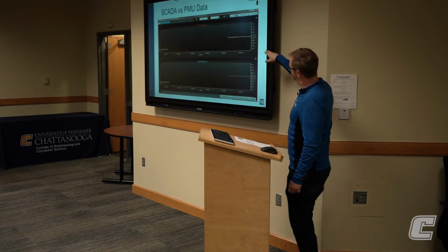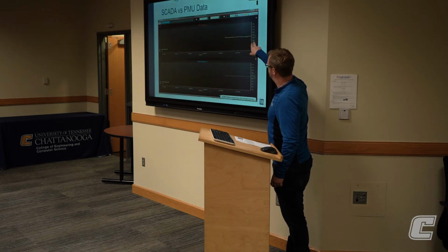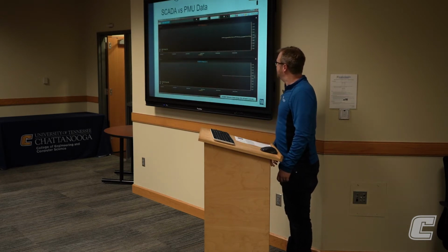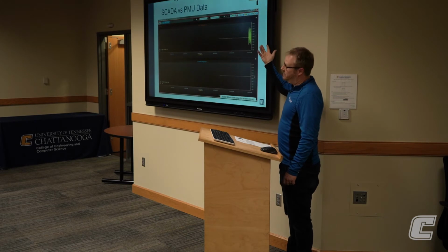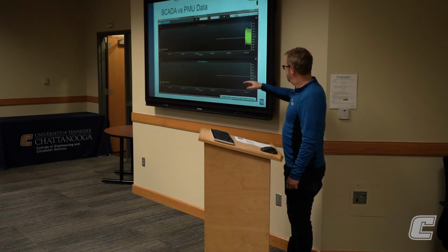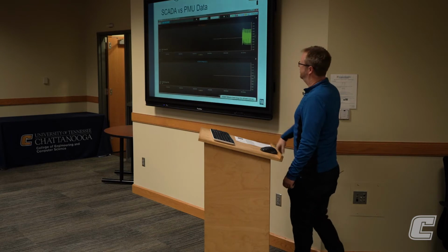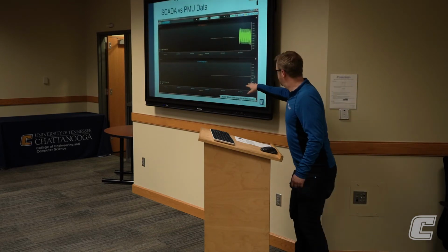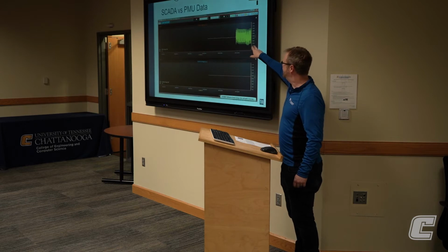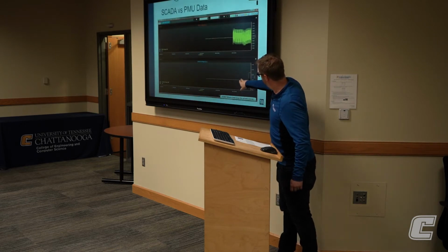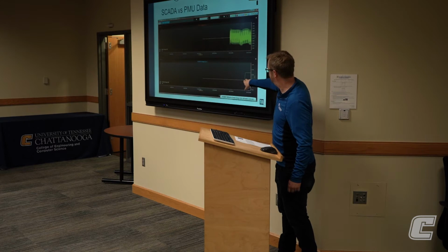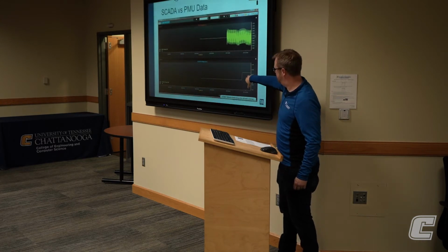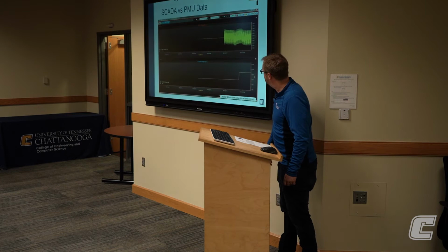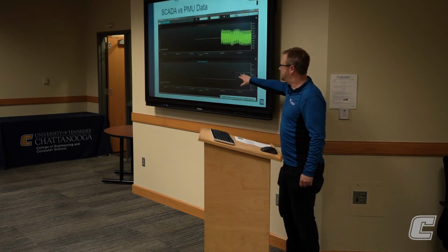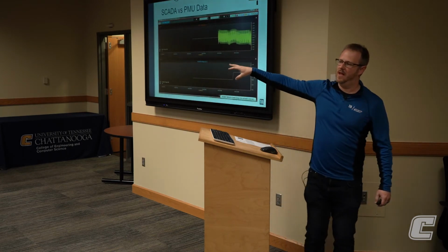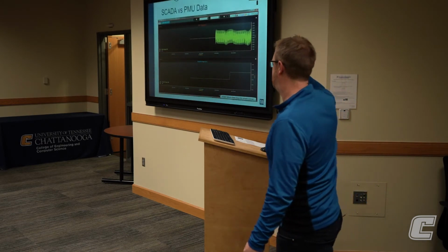You can see what's going on here with the voltage, something's happening at the substation, an oscillation in the voltage signature. But on SCADA, nothing's changed. If you're an operator, SCADA may work in some cases, but wouldn't you rather see this? The average, the mean, isn't changing on SCADA, then it jumps up almost like a step function. You see it, but you're missing a lot of the story, and that's the beauty of synchrophasors from PMU devices.